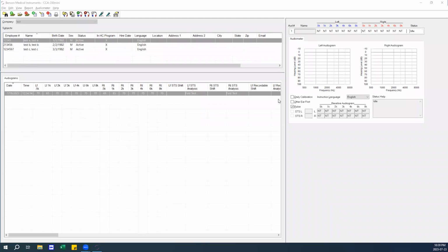From the main operating screen on the right-hand side, there should be a daily calibration dialog box that has to be selected. Once selected, we'll see a check mark inside that box. And then we can hit the start audiogram icon. It's important that once we hit the start button, the room is quiet. We try to avoid any sort of ambient noise if possible.